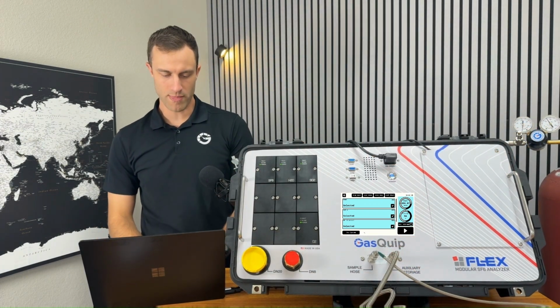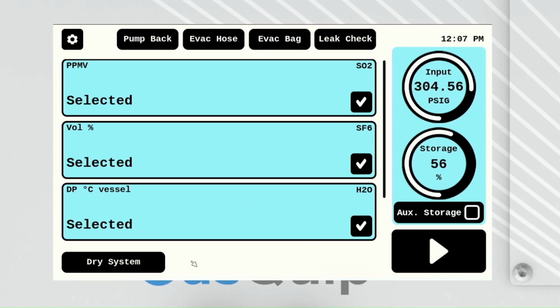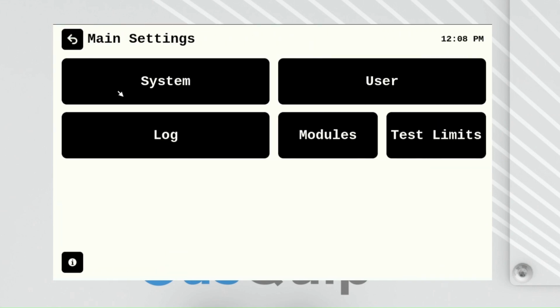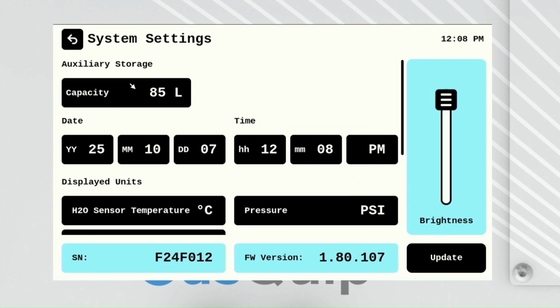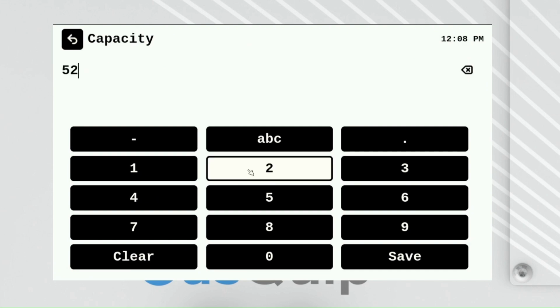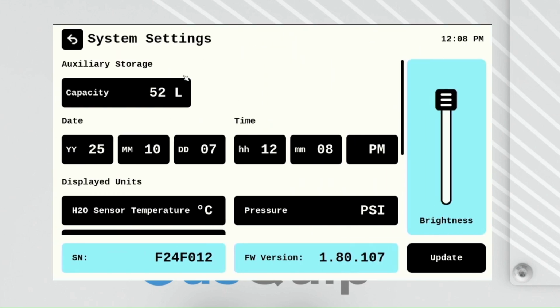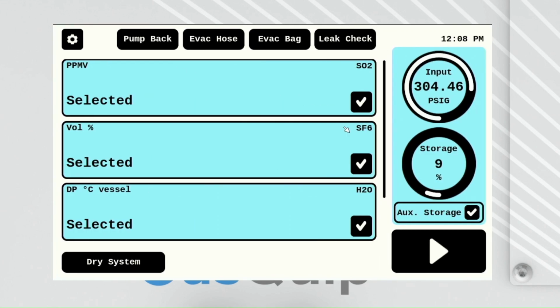On the main screen, we go back to our analyzer close-up here. We click auxiliary storage, and you'll see that our storage has now changed to accommodate the extra auxiliary storage. That tells the system that we now have an extra 52 liters of storage that we can store gas in. If we're using a different gas recovery bag, I need to change this, so we need to go back to 52 liters, and that'll tell the system that we're adding 52 liters of storage. If we had to disconnect it for whatever reason, just uncheck that and it tells the system that we're going back to just what's installed inside of the Flex.